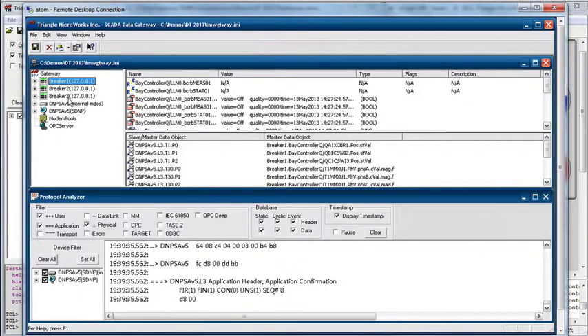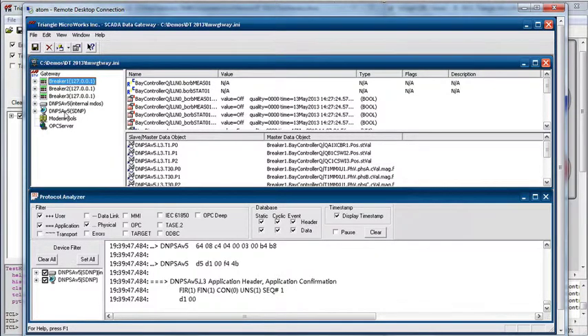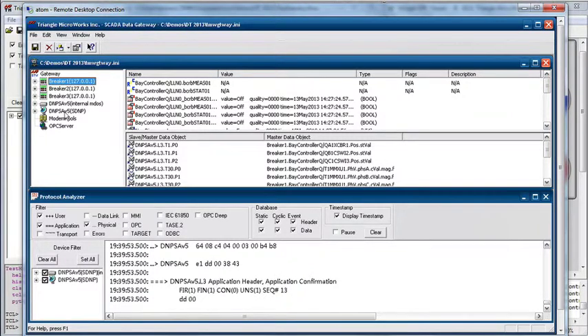We also have a DNP3 outstation channel configured running DNP3 Secure Authentication version 5. We're mapping points from those three IEC 61850 connections to the DNP3 connection. All of these names are user configurable, so in a real-world application you can name them whatever makes sense.